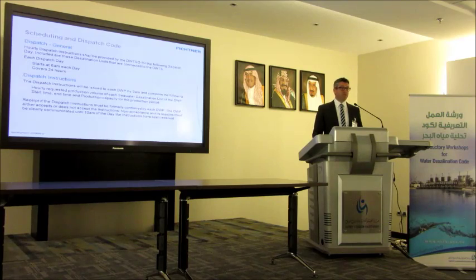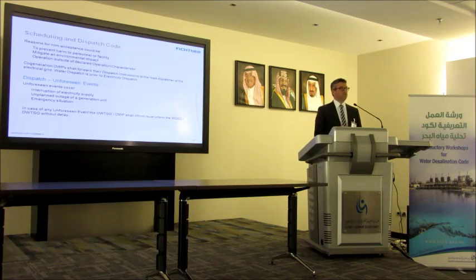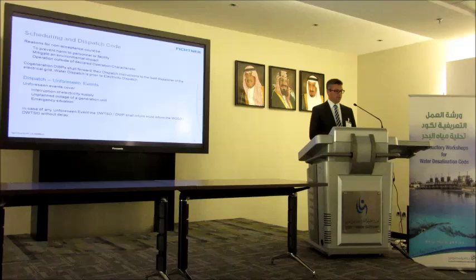This non-acceptance with the reasons must be communicated quickly and within 1 hour, basically, after the instructions have been received. As said, reasons for such non-acceptance could be preventing harm to personnel or facility, mitigating environmental impacts, or an operation outside of declared operational characteristics.